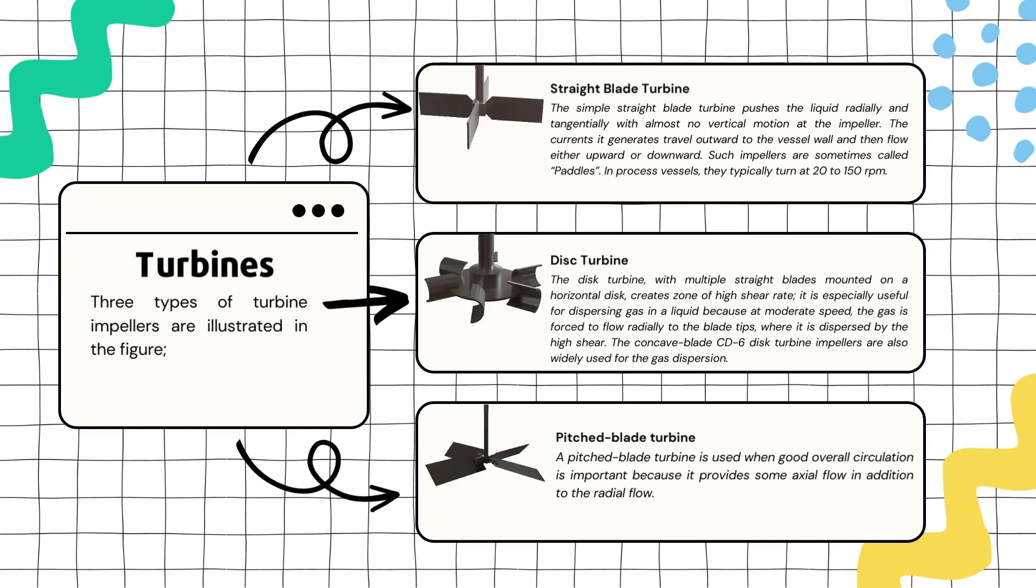The high shear force helps disperse the gas into tiny bubbles for efficient mixing. After disc turbine comes the concave blade CD6 disc turbine. Similar to the disc turbine, the CD6 version has blades mounted on a horizontal disc. It's also commonly used for dispersing gas in a liquid.